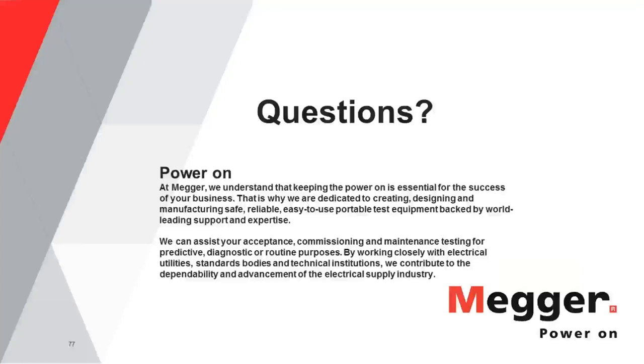And just to give a general idea of magnitude, about a 10 degree centigrade rise will cut insulation values about in half. So it's quite pronounced. And you definitely do, especially if you're keeping records, you do need to include the temperature in any kind of test result. And you can very often correct to a common temperature base. Software can do that for you. So very often you may be working with software or with an instrument that has it built in where you can correct to a temperature base.